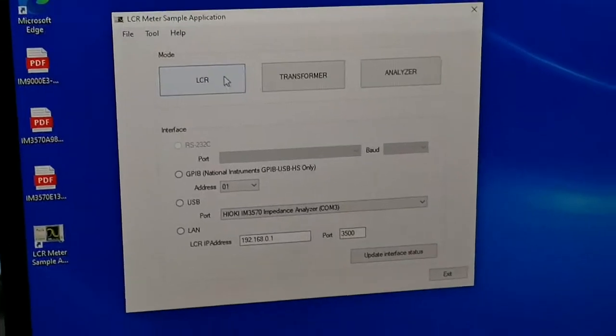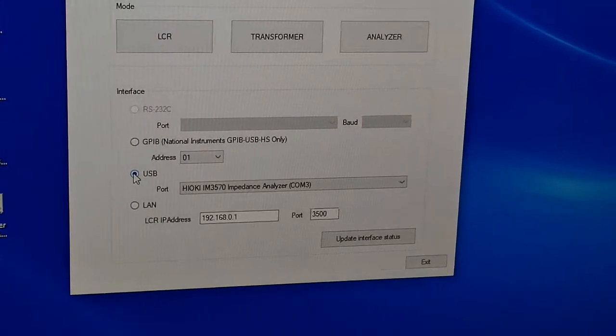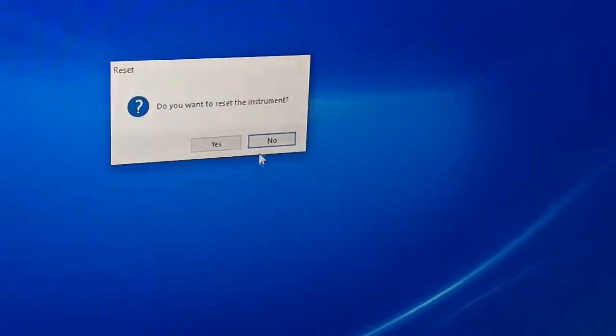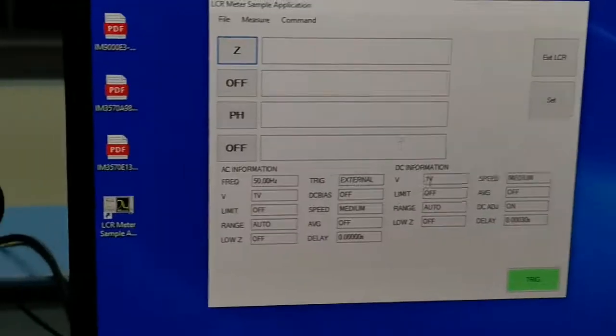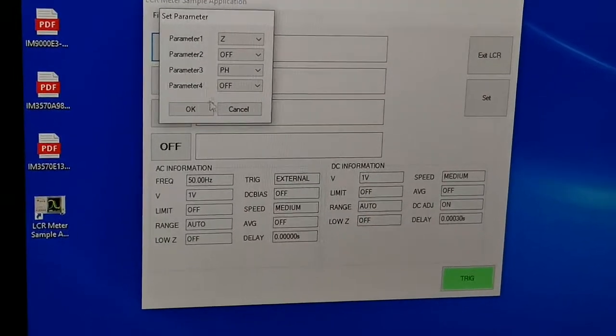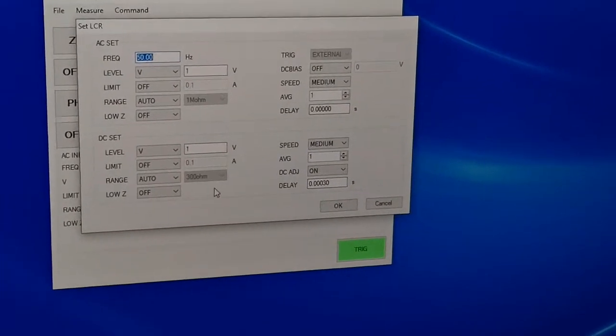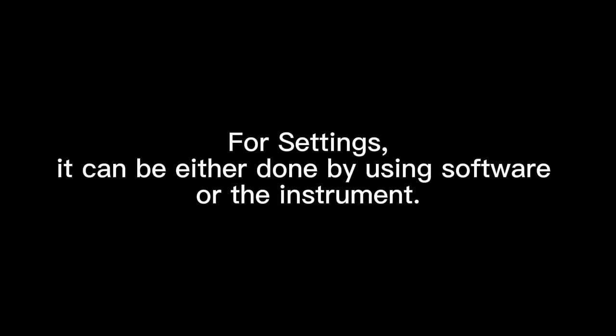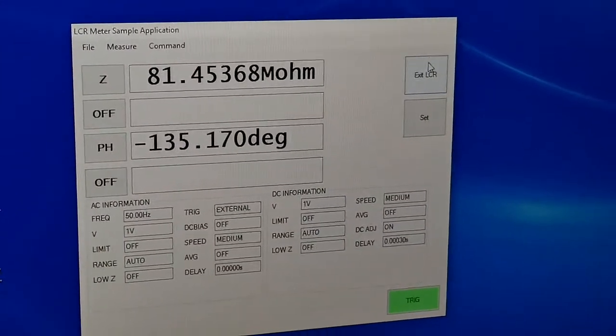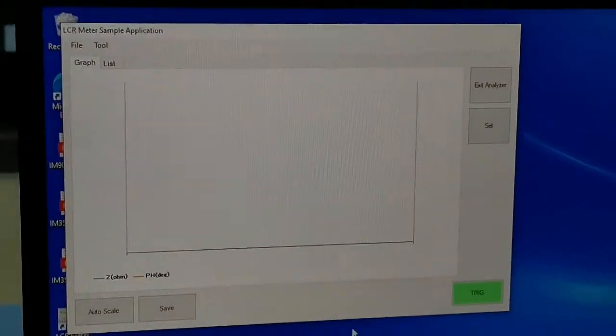If you control from the software, same thing — first you select the LCR mode. You must select the USB because this is using USB. Calibrate already done. This is the parameter — you can select all the parameters. All the settings you can do here, same thing, but the calibration you cannot do here. You can see the reading here.